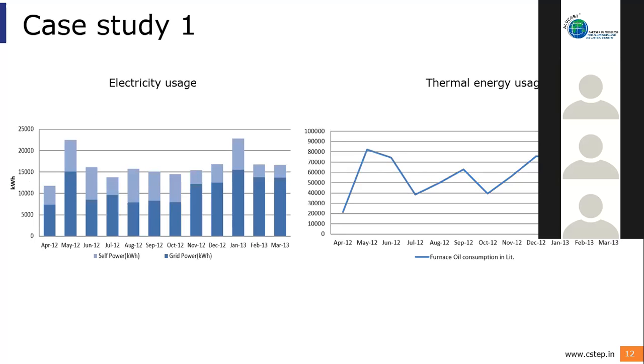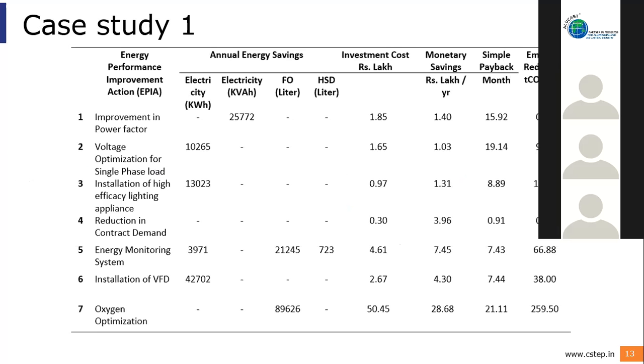This is the monthly variation of the energy consumption. We had recorded this data for the entire year. Next, please. And these are the areas which have been identified in this particular unit. It takes care of the power factor, voltage optimization for the single phase loads, installation of high efficiency lighting, contract demand reduction, energy monitoring, the installation of VFDs, and there is an oxygen optimization in the furnace.